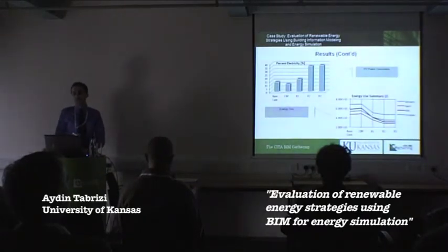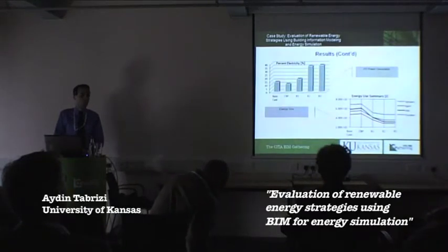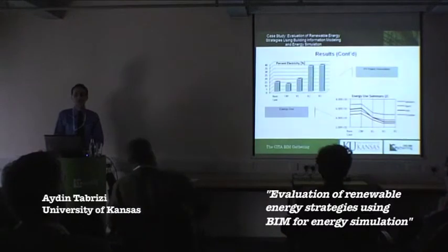So for our results, since we wanted to evaluate what's the generation and what's the consumption, we noticed that the energy generated by the PV panels has decreased from base case to current building performance. But when we introduced our retrofit plan from retrofit 1 to retrofit 3, there is a slight change in retrofit 1. But from retrofit 1 to retrofit 3, and 2 and 3 respectively, we have a dramatic change when we increase the number of PV panels and replace the efficiency of the panels.